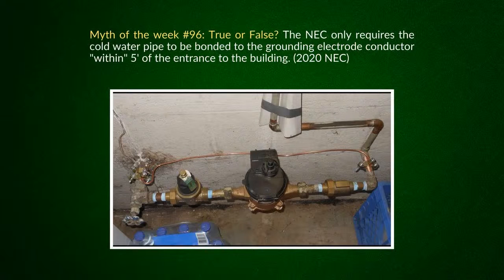And so that's basically what this myth is based off of. I know it was a little tricky for me to get the wording right, and it's close, but probably not 100% accurate. I was just trying to get my point across that the myth is that you don't have to jumper that, all you have to do is hit that water entry location. That was the whole thing I was trying to drive with this myth this week. There's a lot of guys out there who say, well, the code doesn't say you have to jumper that. But I know James is gonna do a good job tonight setting me straight, making sure I understand which code reference requires us to jumper that.